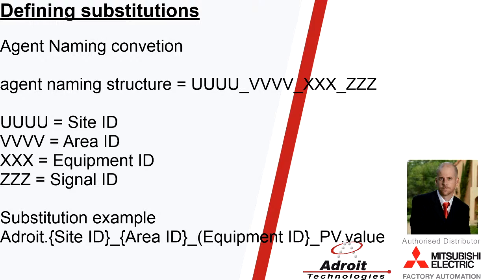So I can create multiple of these feeder or conveyor objects within my structure, and I can then just add the unique IDs for each one of those into that substitution, and that would then create a fully qualified data element, which would then allow me to bring back that information. So this is typically how I would go about defining my substitution.